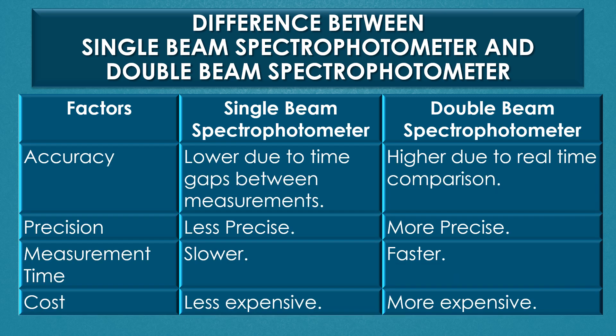Accuracy: the accuracy of a single beam spectrophotometer is lower due to time gaps between the measurements, but in a double beam spectrophotometer, the accuracy is higher due to real-time comparison. Precision: the single beam spectrophotometer is less precise in nature, but the double beam spectrophotometer is more precise in nature.